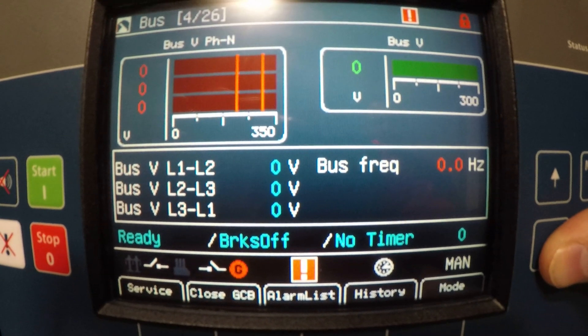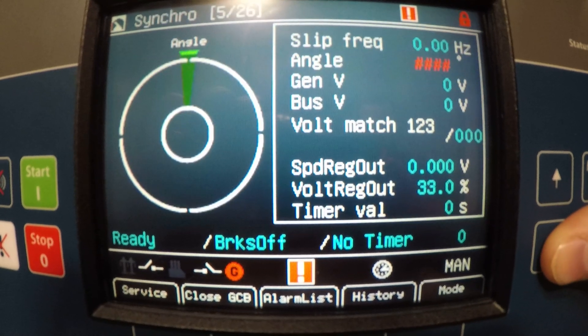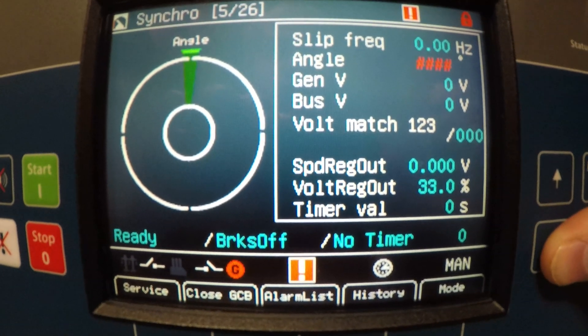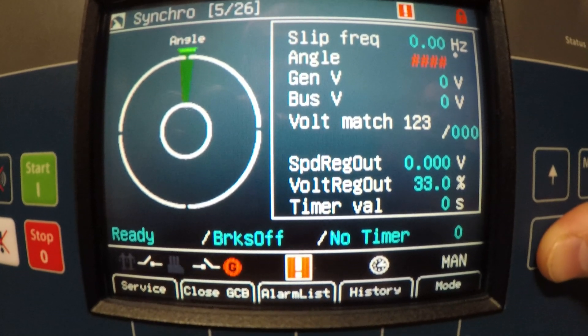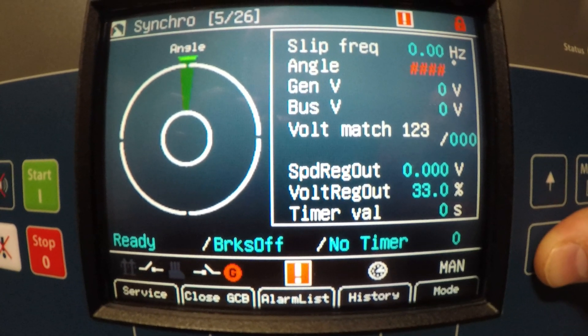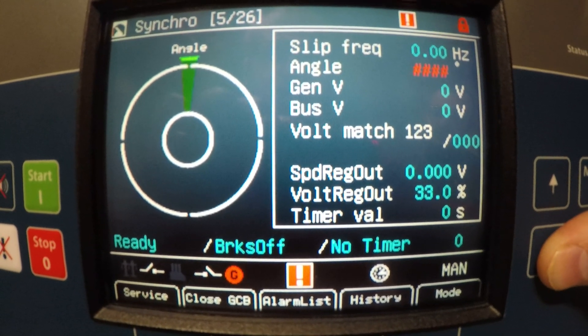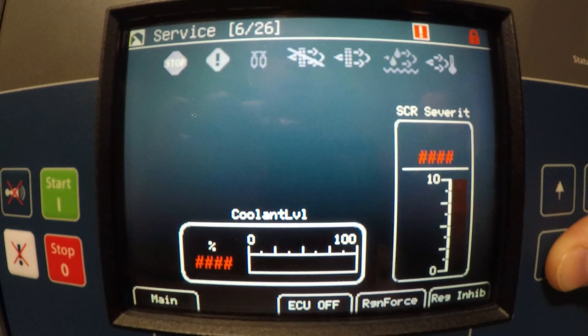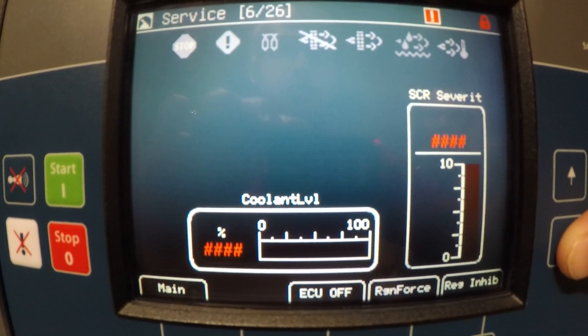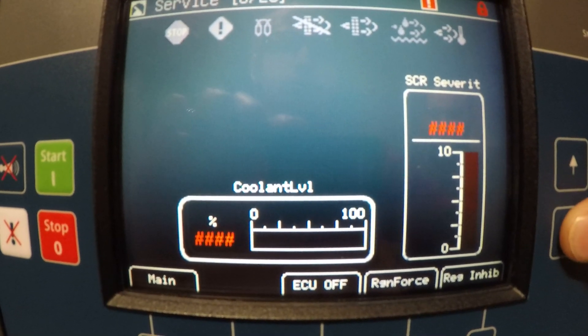You got bus readings — line-to-line voltage readings and frequency. This is your synchroscope for paralleling, which is going to be your angle at which the genset parallels to the secondary genset. You got some service information which would be your SCR and your coolant level.